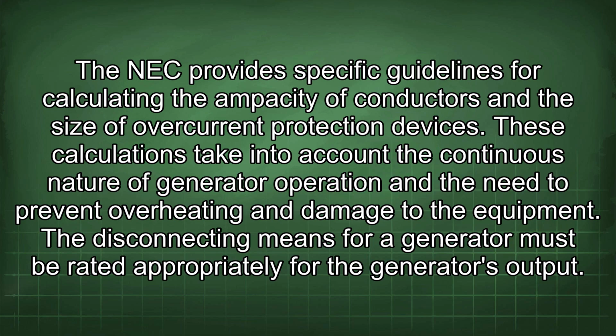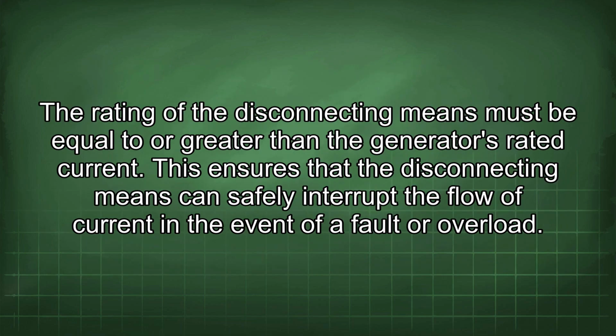The disconnecting means for a generator must be rated appropriately for the generator's output. The rating of the disconnecting means must be equal to or greater than the generator's rated current. This ensures that the disconnecting means can safely interrupt the flow of current in the event of a fault or overload.